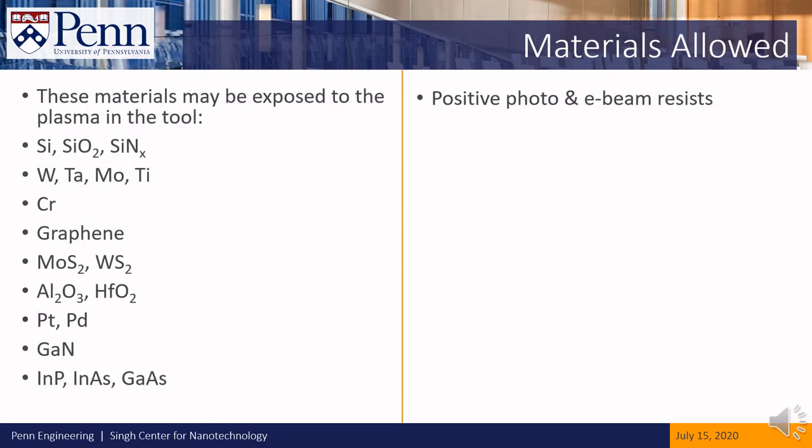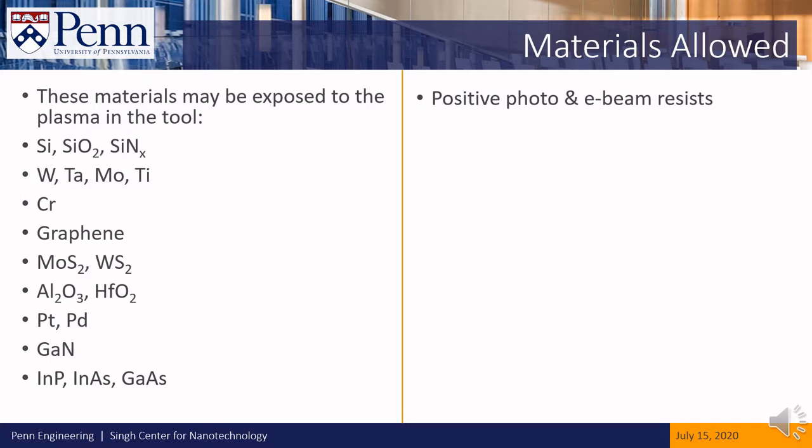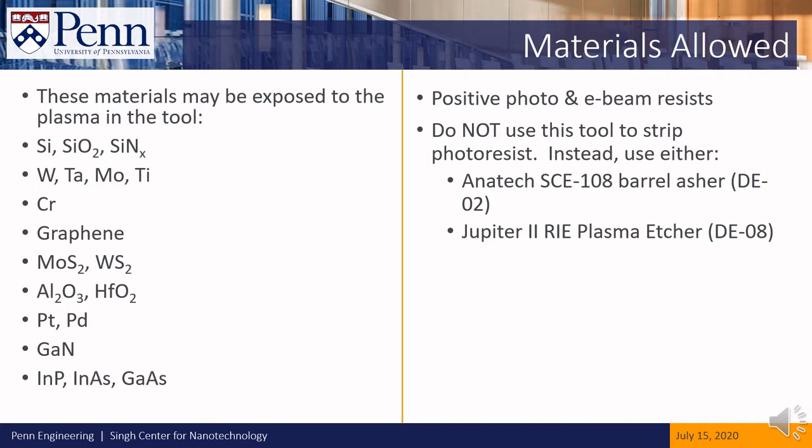These materials are allowed in the tool. Although photoresist is allowed, you must not use the Oxford 80 to strip the bulk of your photoresist. To do that, please request training on either the Anatec barrel asher or the Jupiter 2 plasma etcher.